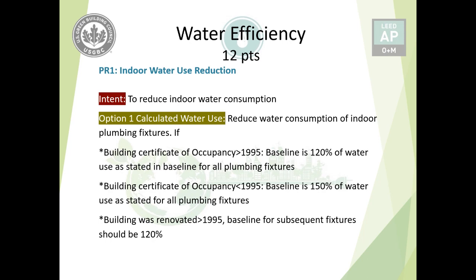Back when the buildings were constructed, the codes or the use of water were not that stringent. So they are giving a flexibility that if the building was occupied after 1995, you have 20% more flexibility, and if it was before 1995, you have 50% more flexibility from the standard baseline. Only the portion that is renovated after 1995 has to follow the 120% baseline, and the one that is not renovated will follow the 150% baseline.